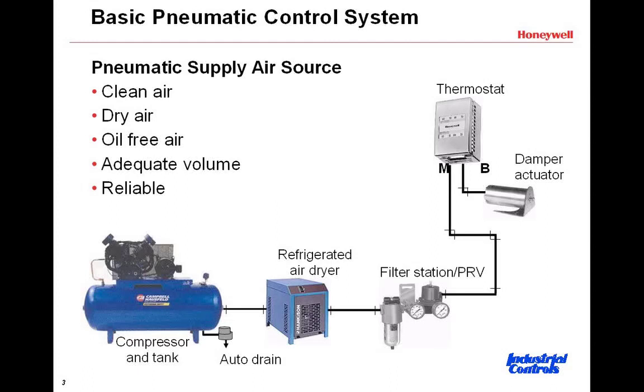As far as the tank itself and things that we've been talking about, what are the results — what happens when this auto drain is not working properly? Well, you'll find, first of all, that the cycle time will change because some of the internal volume of the tank is consumed by water.